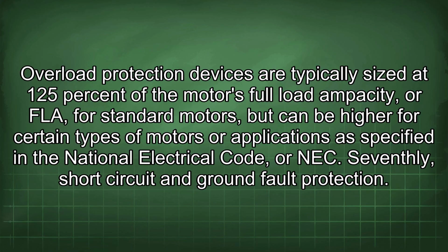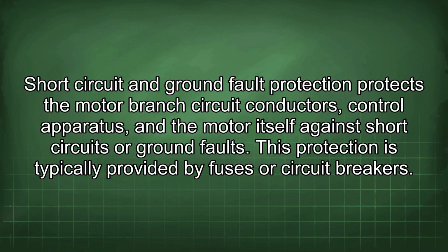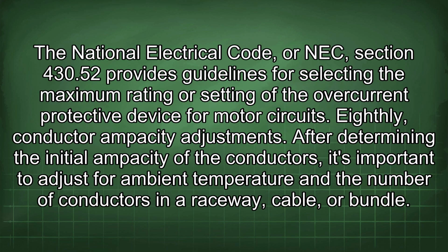Seventhly, short circuit and ground fault protection. Short circuit and ground fault protection protects the motor branch circuit conductors, control apparatus, and the motor itself against short circuits or ground faults. This protection is typically provided by fuses or circuit breakers. NEC Section 430.52 provides guidelines for selecting the maximum rating or setting of the overcurrent protective device for motor circuits.